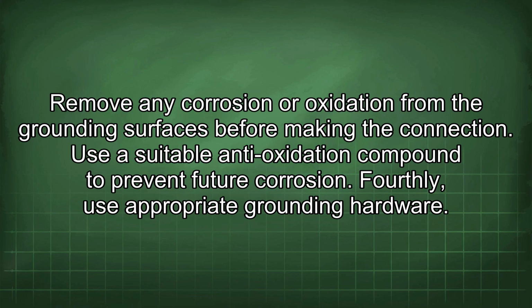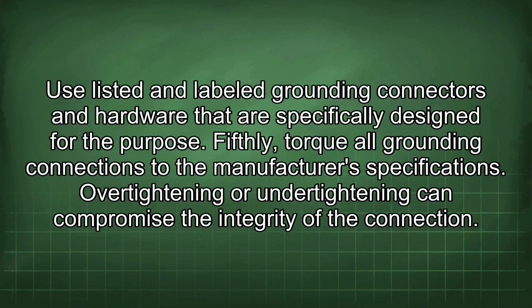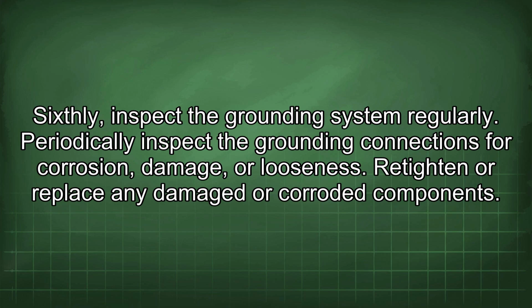Fourthly, use appropriate grounding hardware. Use listed and labeled grounding connectors and hardware that are specifically designed for the purpose. Fifthly, torque all grounding connections to the manufacturer's specifications. Over-tightening or under-tightening can compromise the integrity of the connection. Sixthly, inspect the grounding system regularly. Periodically inspect the grounding connections for corrosion, damage, or looseness. Retighten or replace any damaged or corroded components.